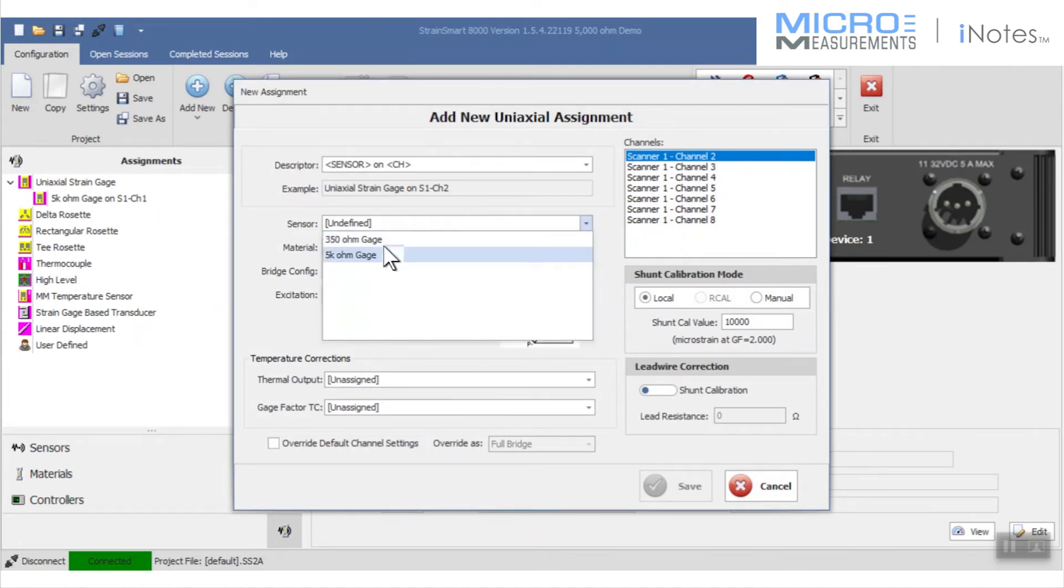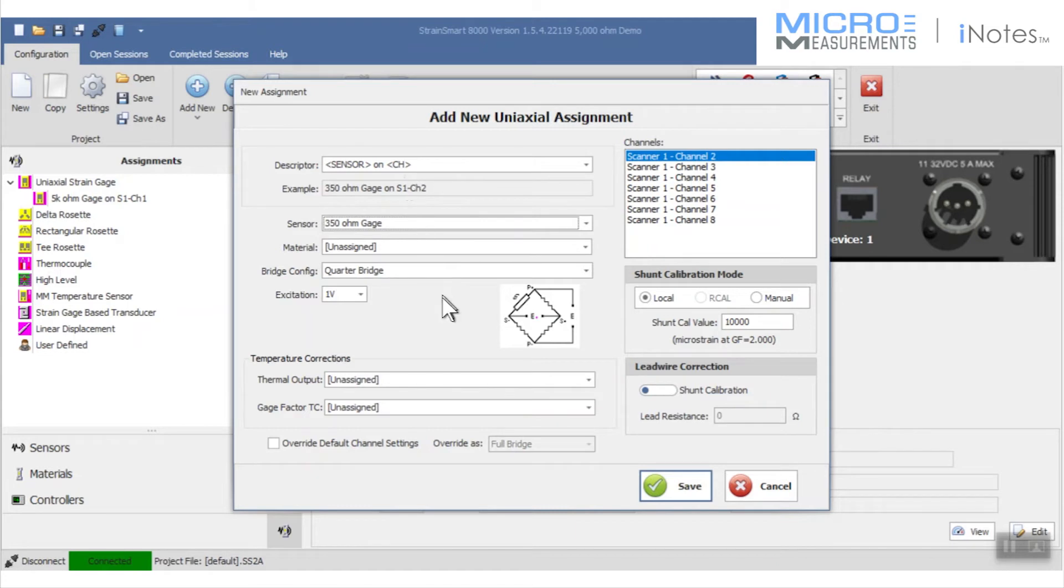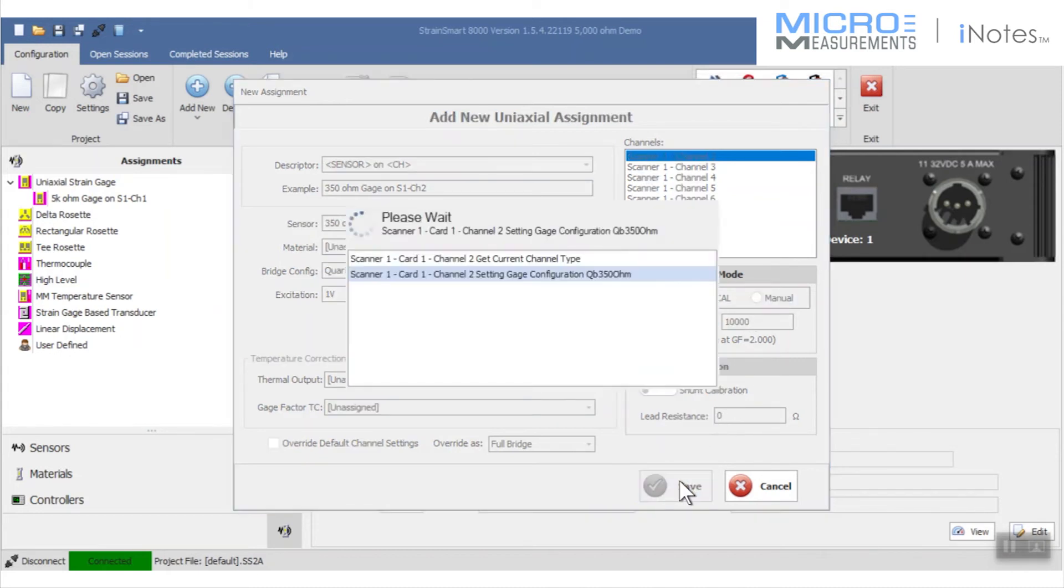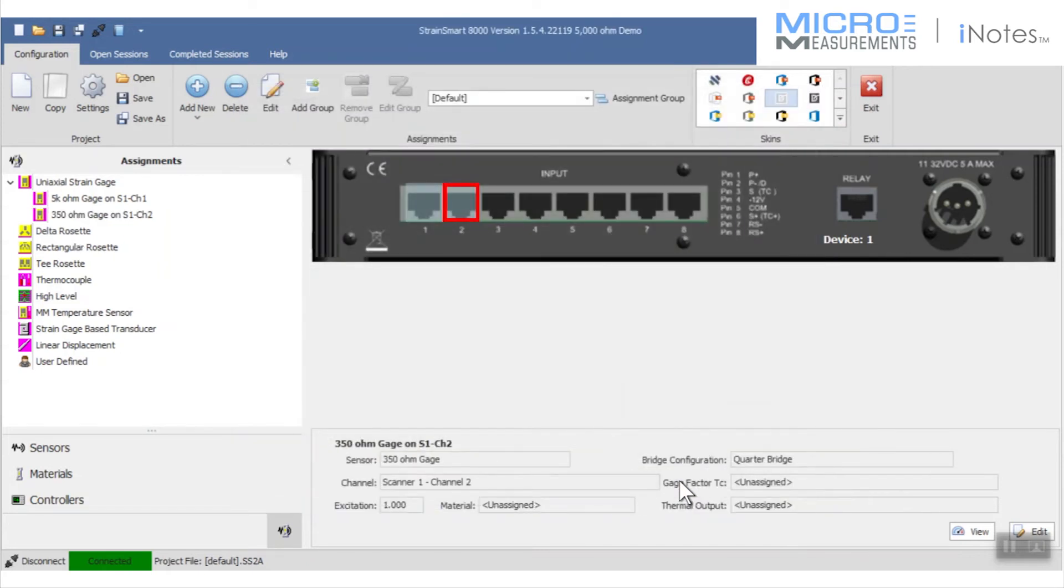So I'm going to take my other 350 ohm sensor and assign it to channel number two. I'm going to leave everything else the same because it's expecting a 350 ohm gauge, and the shunt calibration procedure will hopefully find the correct value if there are not any mistakes either with the strain gauge connection or the shunt calibration process itself.